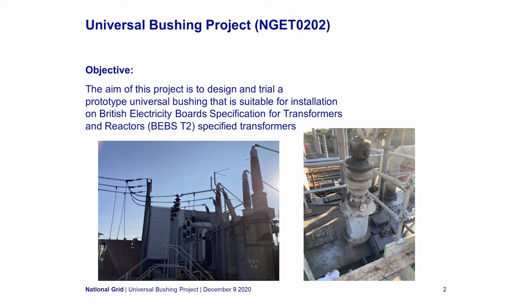Well-designed transformers can remain on the network well beyond their original design life. We have many transformers now that are over 50 years old, and some that are over 60. During these long lifetimes, the bushings can develop problems that mean they need replacement. Bushings are designed to be replaceable items, although it's not always particularly easy. To facilitate these changes, we hold spare bushings in stock, because lead times can be several months.